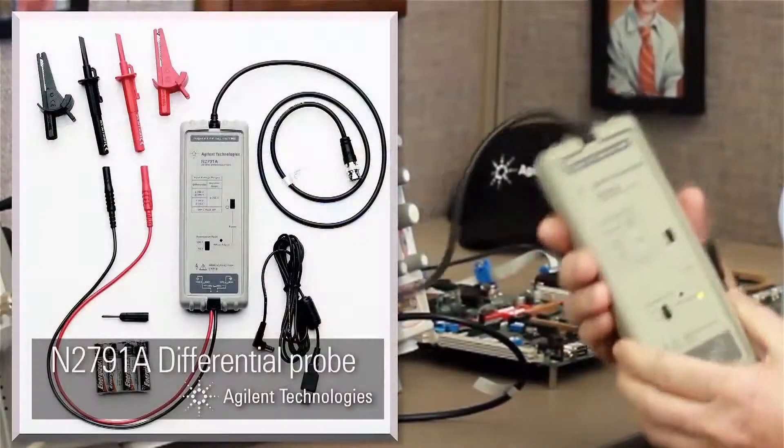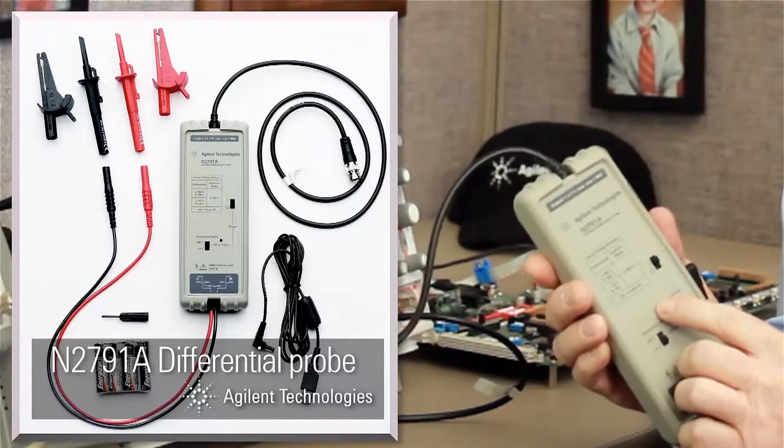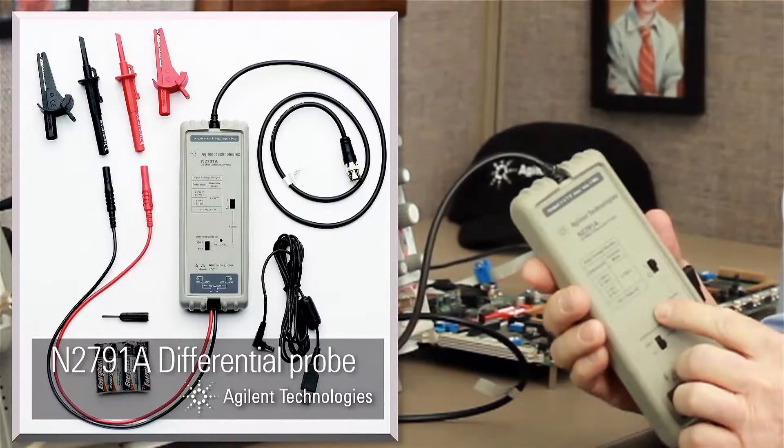In this short video, I will show you how to set up the Agilent 3000 X-Series oscilloscope to trigger on and decode a CAN serial bus. The first step is to probe the differential CAN bus. Agilent recommends using the N2791A 25 MHz differential active probe. Let's begin.